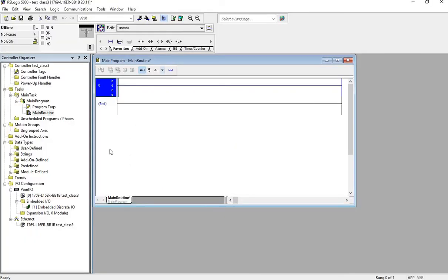On the Logix part, the Logix controller that I'm using today is a 1769-L16 CompactLogix. If you are using class 1, you need to add the add-on profile under the Ethernet tab so that you have I/O connections to the PLX31 gateway. But if you are using class 3, it is not necessary to do this part. What you need is just messaging instructions, like how you do messaging between CompactLogix, ControlLogix, and some other Ethernet devices.